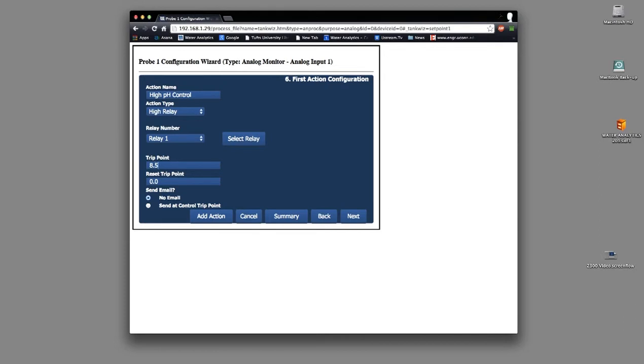For a control of a rising process, the reset point has to be less than the trip point. You don't want a reset point that's too close to the trip point, otherwise your relay will be going on and off frequently. So I'll pick 8.2. That's the pH at which the relay turns off. And this is just a relay, so there's no need to send an email when the pump turns on. So I'll keep the no email button.